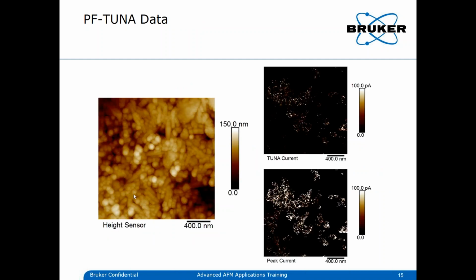Here you can see images from a height sensor, and simultaneously you can select up to 8 channels in all peak force modes. You can have the TUNA current, the peak current, and the contact current in the same image, and you get a map of your current distributions, which allows you to see where you have areas of higher or lower conductivity.